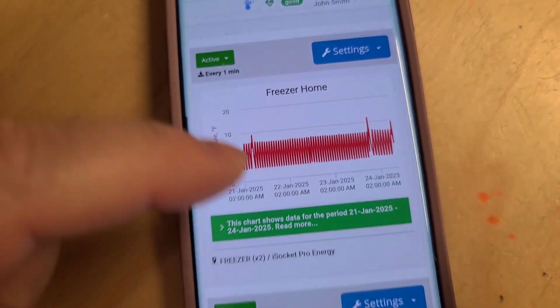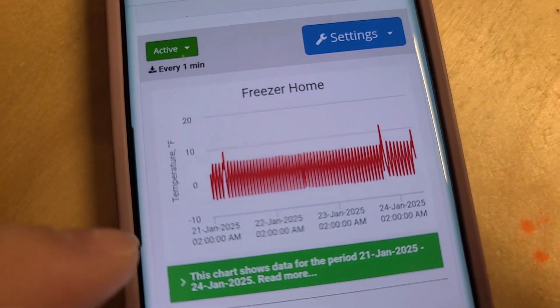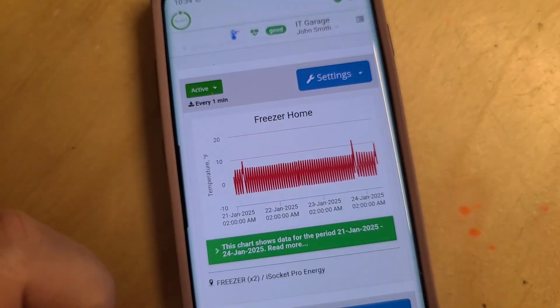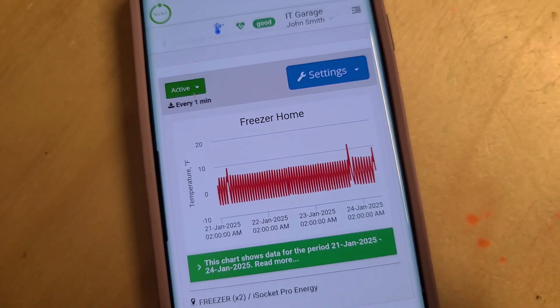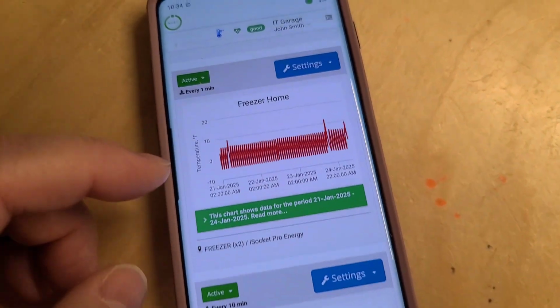And when the compressor stops or starts, we see changes between -5 and +5 Fahrenheit. I wanted to say that these peaks happen just in that location of the sensor. So I can relocate it, and probably in another place it will be different.